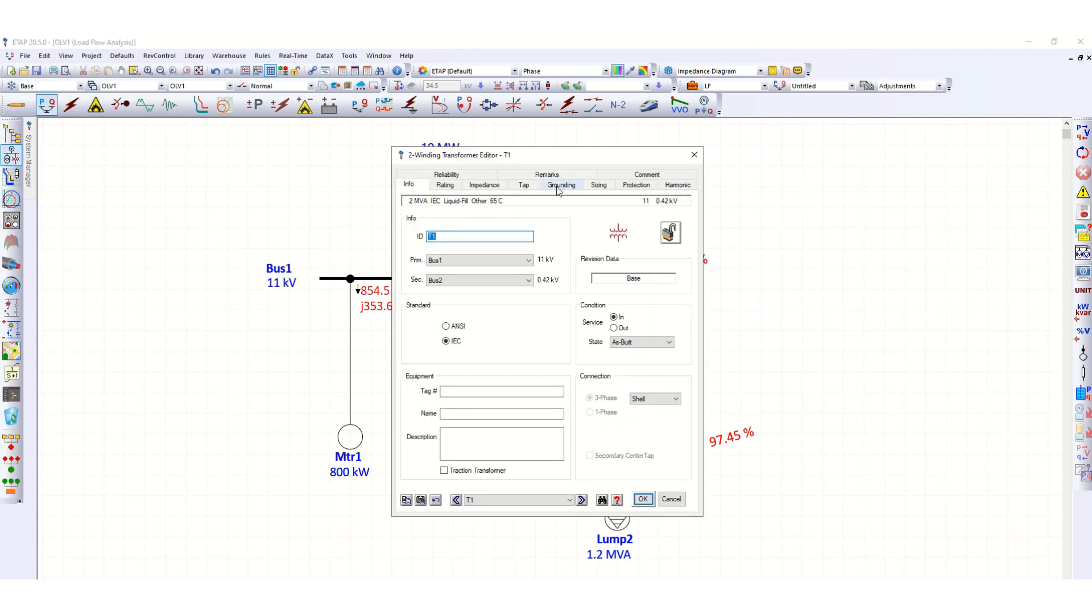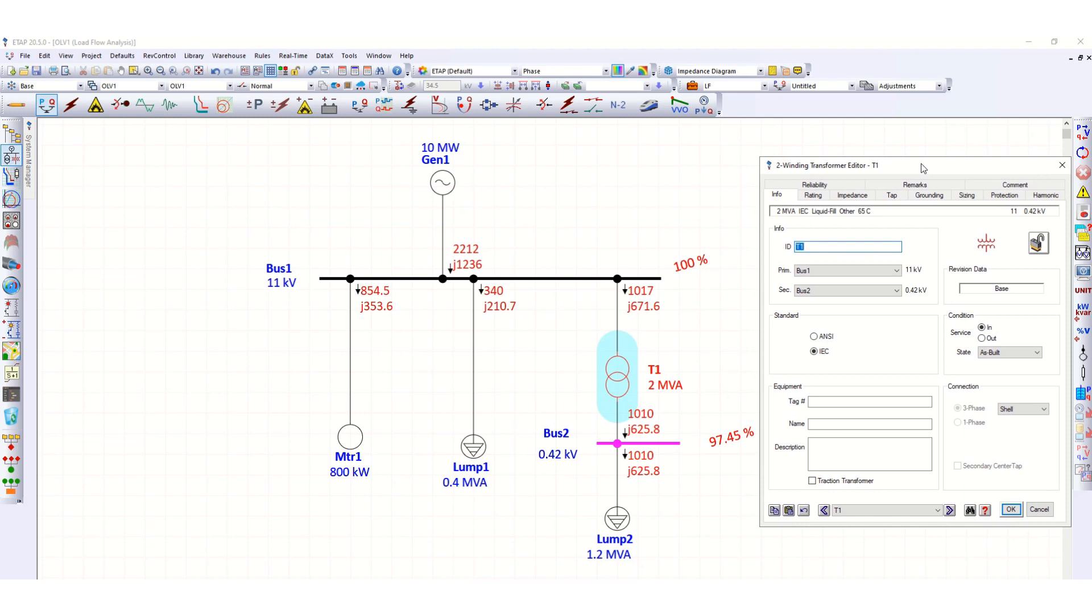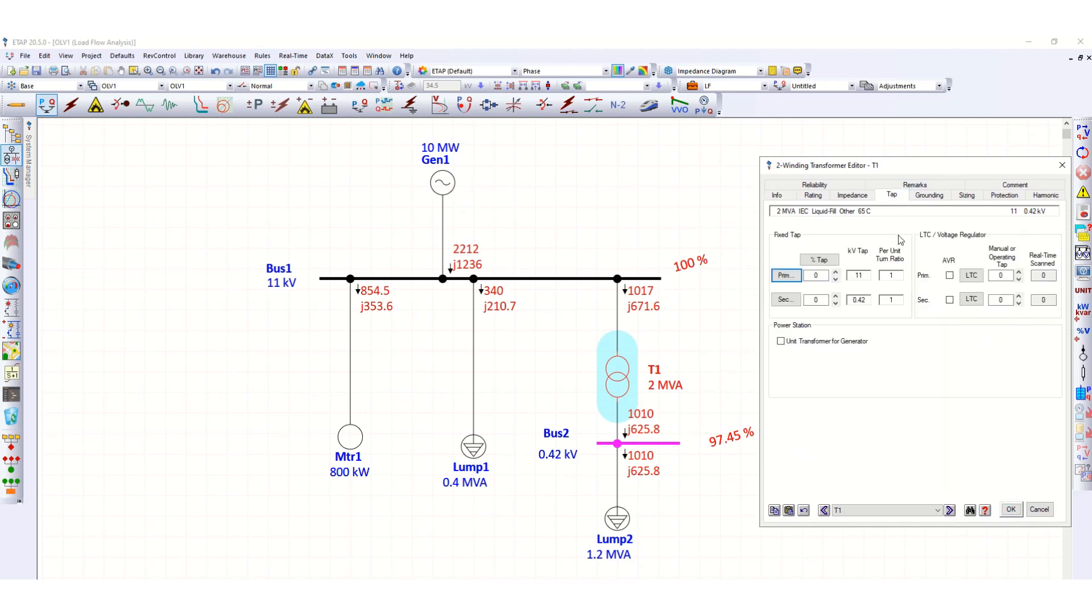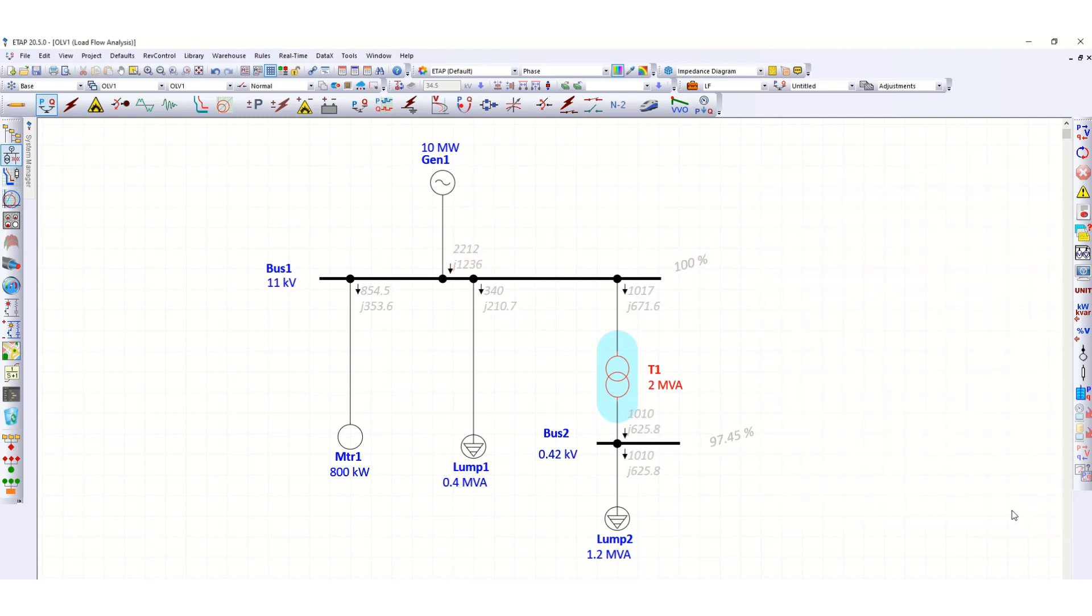Now if we change the transformer tap position here, suppose going to the positive side, plus 2.5 percent at primary side, then we will check this bus voltage.